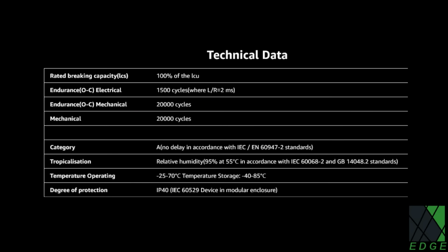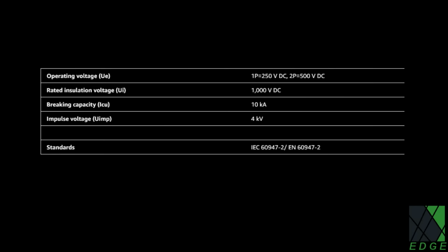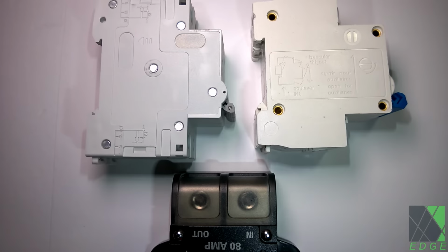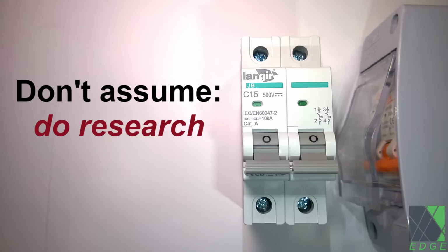Quality circuit breakers usually have detailed specifications listed, and you should read them before buying. Avoid cheap circuit breakers that make false claims and/or don't have proper specifications listed. A circuit breaker can't protect your investment of wiring and equipment if it doesn't work as expected. Assumptions can be deadly. It's important to do the research and ensure you have the right circuit breaker for the job and that it will really protect the system if there is a fault.